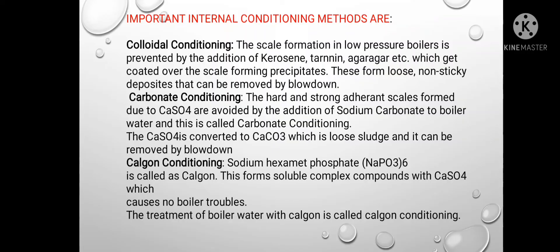Second, carbonate conditioning — the hard and strongly adherent scale formed due to CaSO₄ is avoided by the addition of sodium carbonate to the boiler water; this is called carbonate conditioning. The CaSO₄ is converted to CaCO₃, which is a loose sludge and can be removed by blow-down. Third, calgon conditioning — sodium hexametaphosphate is called calgon. It forms a soluble complex compound with CaSO₄ which causes no boiler troubles. The treatment of boiler water with calgon is called calgon conditioning.